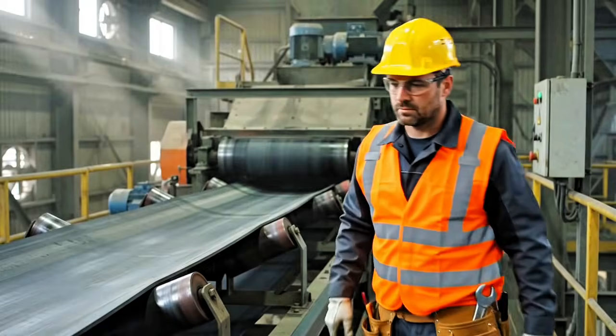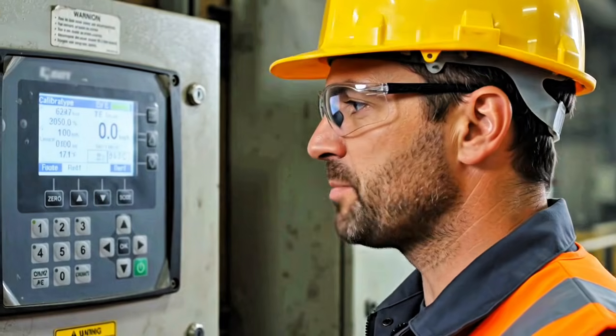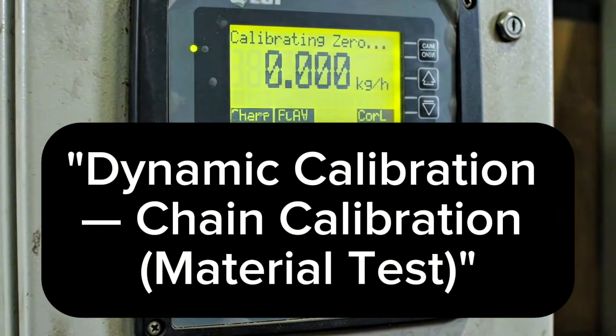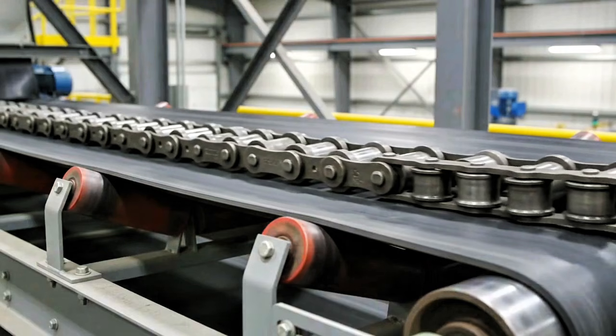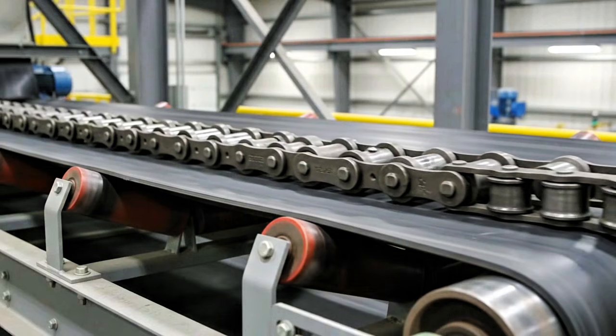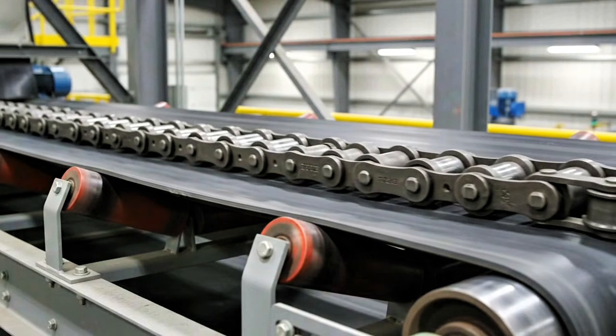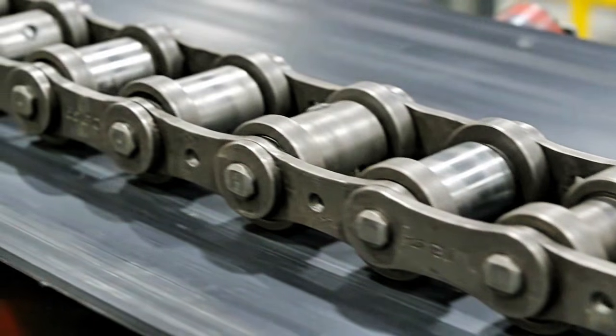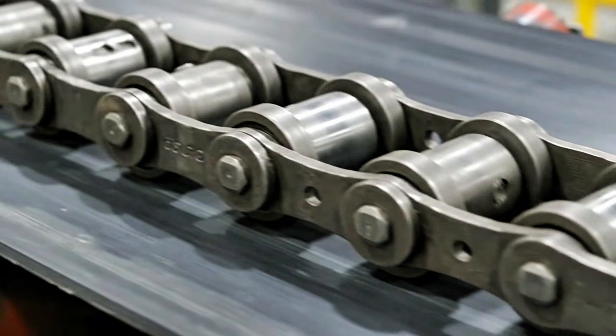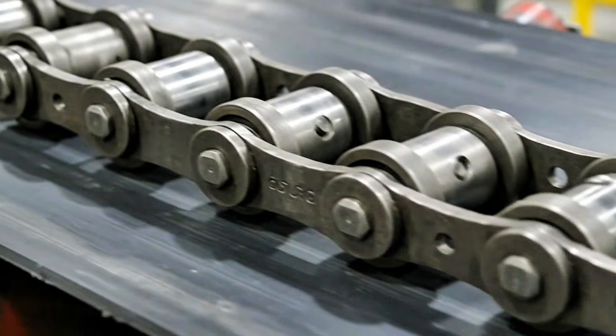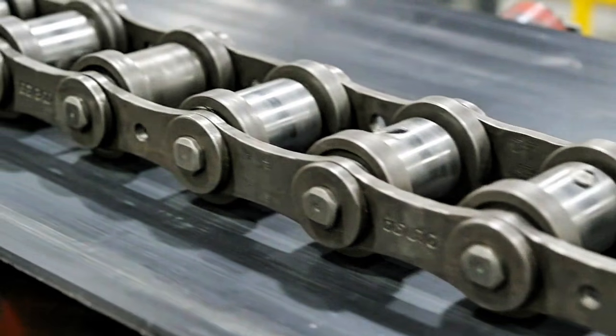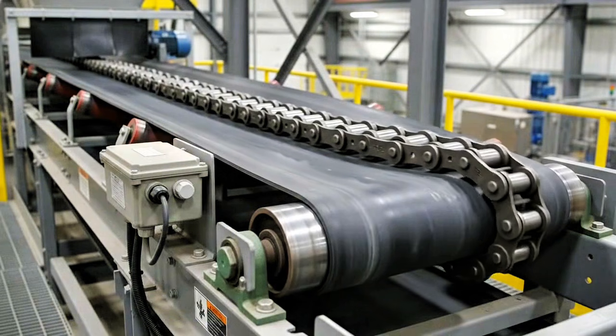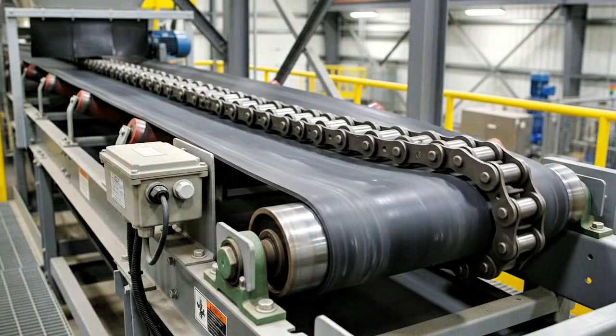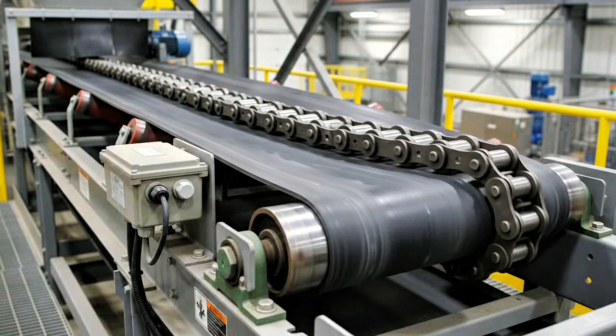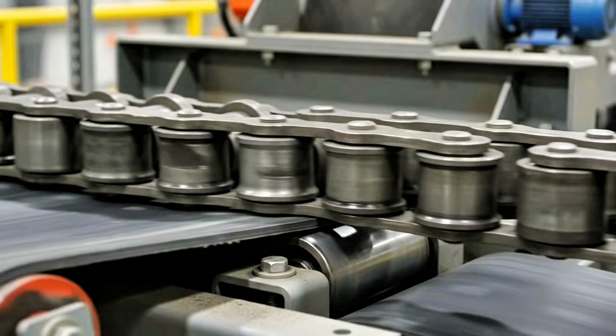That's what dynamic, or material, calibration corrects for. The gold standard method in cement and bulk material plants is chain calibration. You run a calibrated test chain, a chain of known, certified weight per unit length, over the weigh span while the belt runs empty at normal operating speed. The chain simulates a moving material load with a precisely known weight distribution. The controller measures what it thinks the chain weighs, compares that against the chain's certified weight, and calculates a correction factor. Chain calibration should be run at multiple points across the belt width and, where the feeder design allows, run the chain through several passes and average the results, because a single pass can be thrown off by minor belt speed variation during the test.